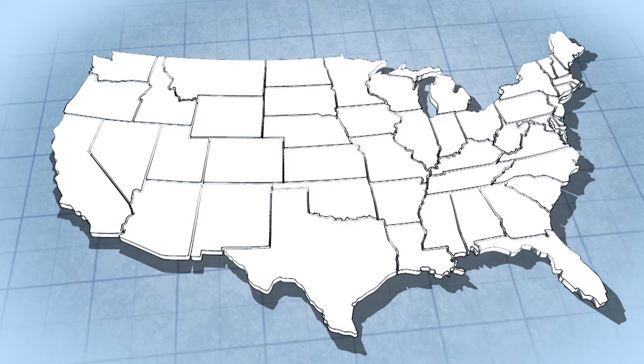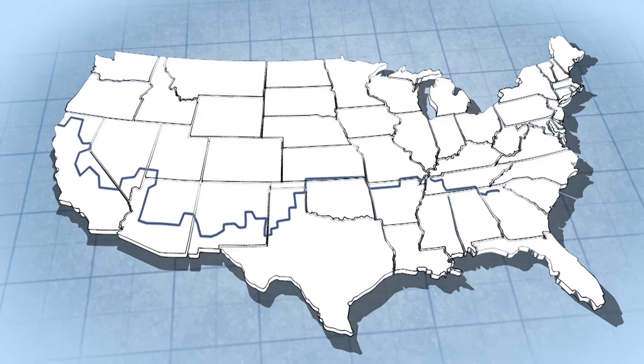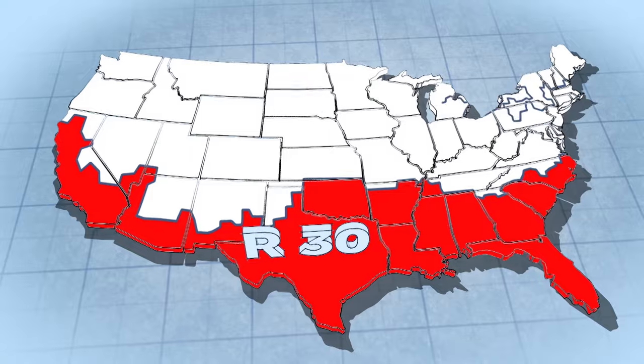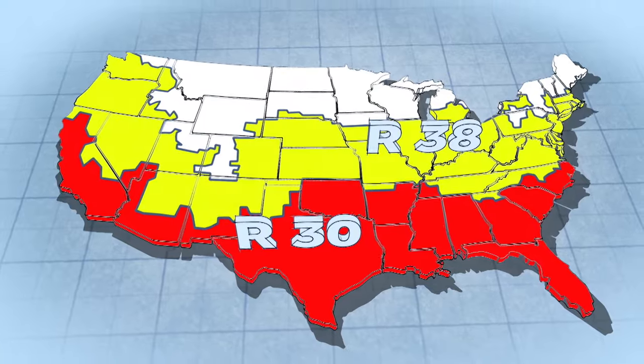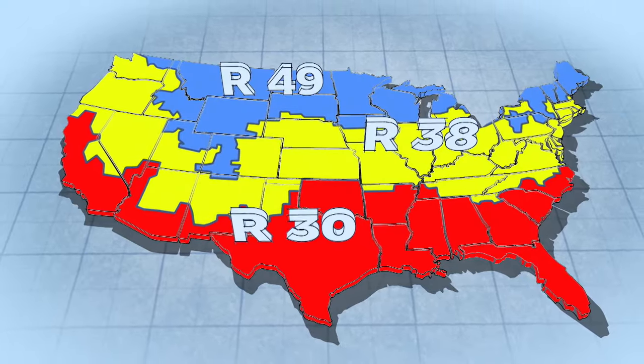When you say where, you're talking about where throughout the house — whether you're thinking about a wall or a roof. Now the biggest heat loss is through the roof. You can always add insulation in your attic, but it's harder to do it in the wall, so you may not be adding as much to the walls. In terms of region: in a warmer climate in the southern part, the R-value required for the roof is R30; the middle of the country, R38; and the cold region up near Canada, R49.